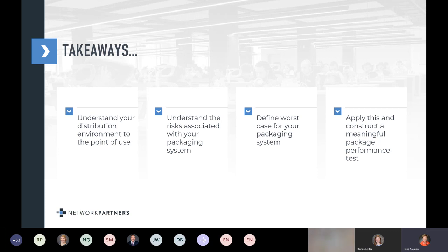But regardless of which one you're using, if you don't pass your acceptance criteria, that's clearly a failure that has to be addressed, with understanding the root cause and determining how to remedy that problem. But if you failed one and passed the other, you still have to go through that root cause analysis.